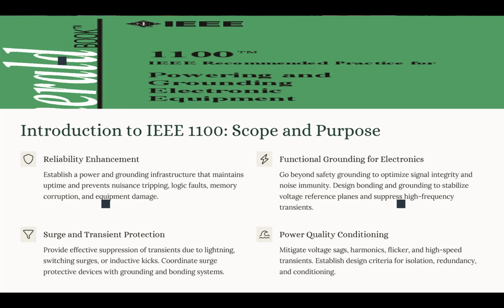So the traditional grounding methods that we had before IEEE 1100 were mostly focused on the safety of the electrical system. They were mostly designed to prevent electric shocks or fire. Now, when we have sensitive electronic equipment like computers, medical equipment, or telecom systems, they also need some functional grounding approach. So we need to prioritize signal integrity, low noise reference planes, and transient suppression.